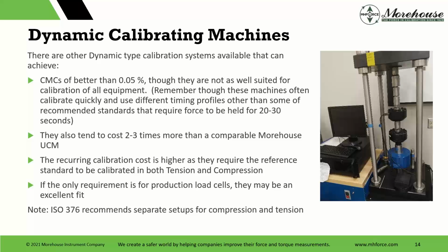Dynamic calibrating machines, that's what I call these. CMCs can do compression and tension in the same setup, usually automated. Space is sometimes limited, and they are not suited for calibration of all equipment. They can calibrate quickly, but they have different timing profiles, and a lot of the standards, ISO 376, require the force to be held for 20 to 30 seconds, and they don't do that well.